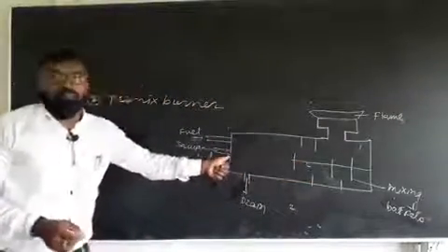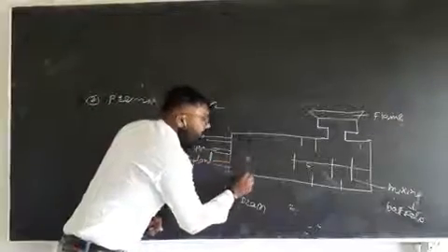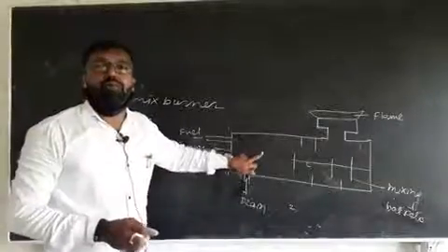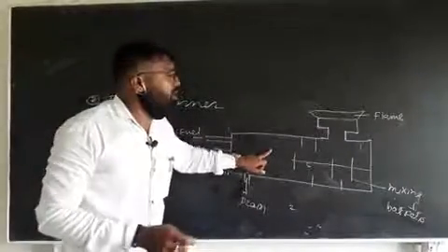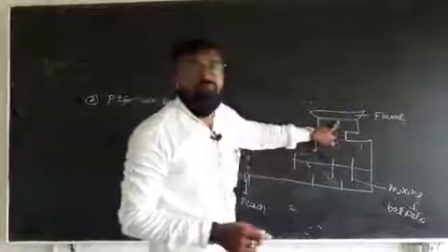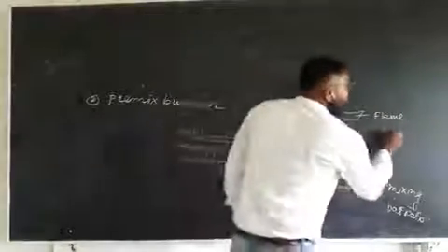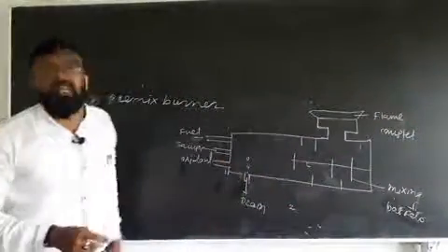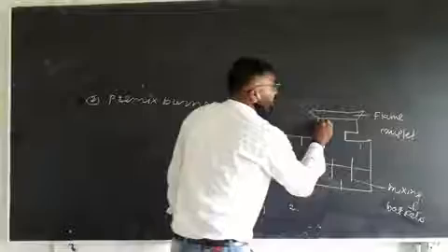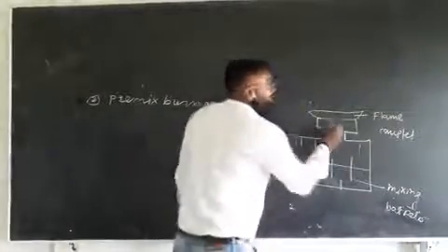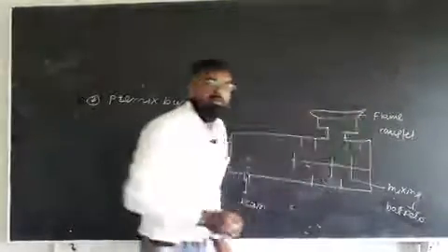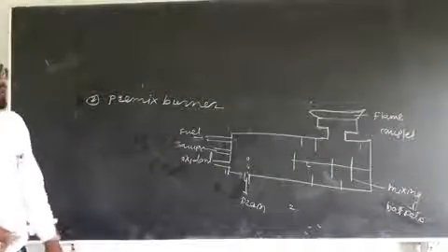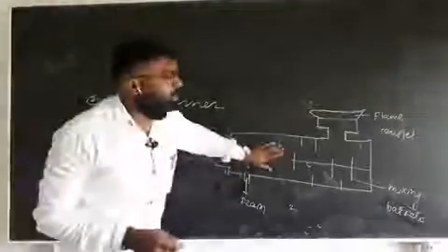In this burner, the larger droplets of the sample are drained out and only a smaller amount, aerosol-like particles, enter the flame, so that complete evaporation can take place. Another advantage of this burner is that the flame width is high, so there is a high surface area available for burning the sample. This one is a premix burner.